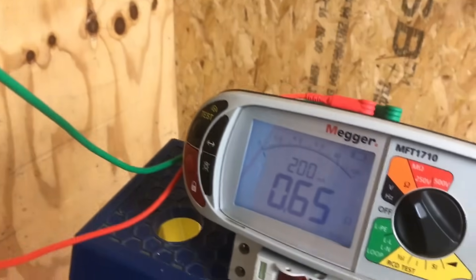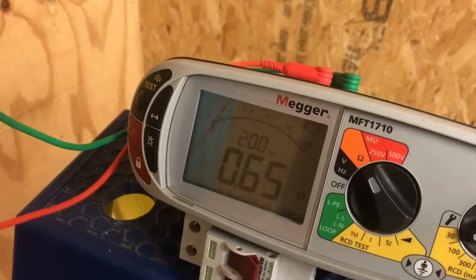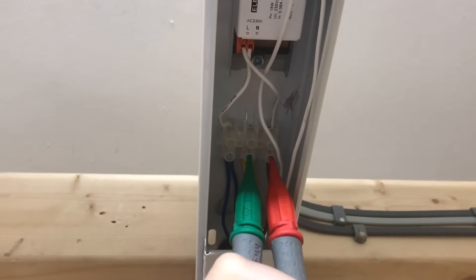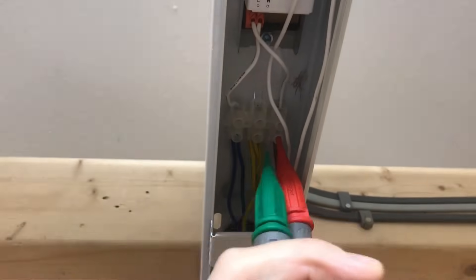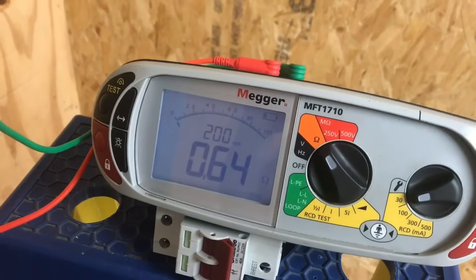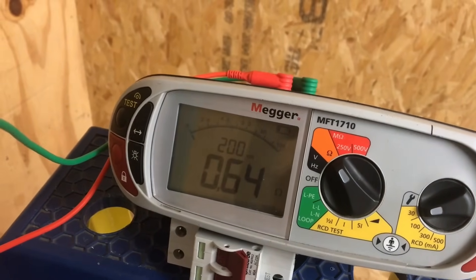All we've got to do is flick the switch, and as you can see we're now getting a much better reading of 0.65 of an ohm. We're happy that we've proved polarity - we've got the line being switched by the switch rather than the neutral. We can now prove beyond a shadow of a doubt that we've got an earth connection to the metal work of the light fitting by connecting onto the back box, and we're getting 0.64 to 0.63 of an ohm.